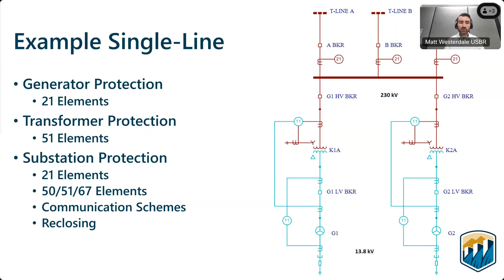The information we need to gather from them to do our coordination study includes their 21 elements, their overcurrent elements, which are typically directional, information on their communication schemes, and understanding how they perform reclosing as well. We've found all this information is very necessary to performing our coordination study, so we ensure we're running the right simulations and scenarios for faults out on the system.